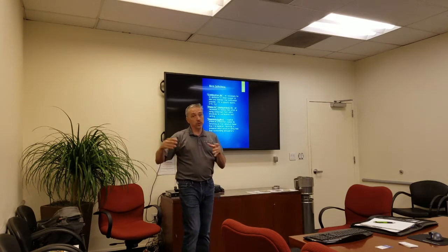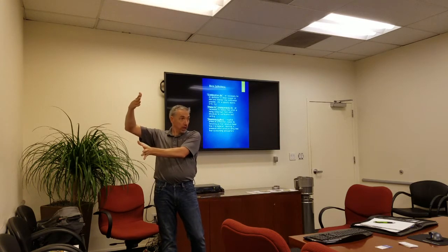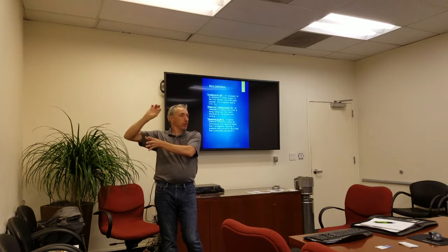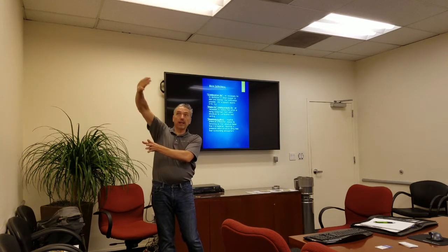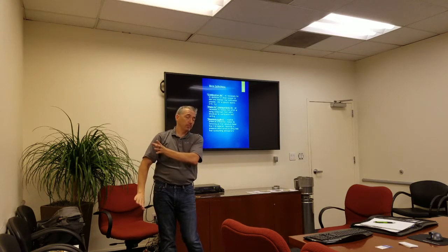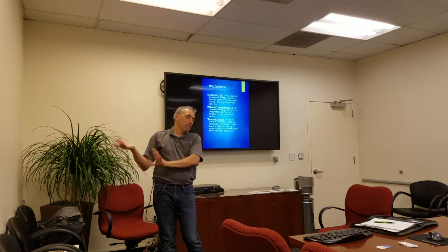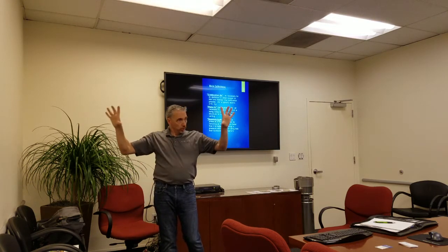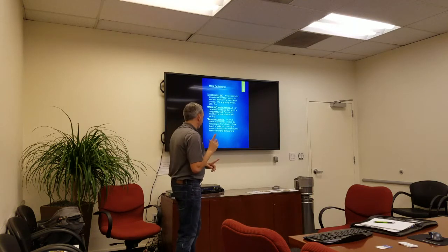As the flue system takes air and the burner takes air, it has to be made up somewhere. So our makeup air is either coming in from vents on the wall. The rule for that is 1 square inch of net-free area for every 4,000 BTUs. And that's an opening at the top within 12 inches of the ceiling, and an opening the same size within 12 inches of the floor. The openings can be different sizes. That's the minimum size opening. And if you put a filter there or a louver, that increases it as well because it's net-free area.